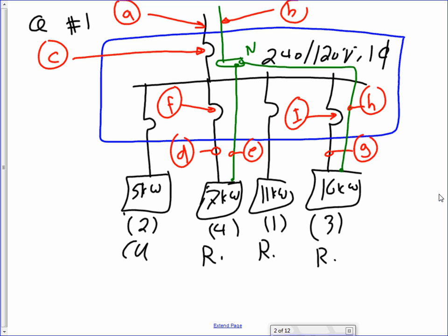So, okay, I'm going to start directly, guys. I'm going to start with sizing A. I do have the calculation here for you. So if you look at A, yesterday we were looking at 220.55, the table 220.55. I want you, Matt, to look at these sizes. Do you guys remember that 5 and 7 are under B? Both of them are under B, right? Remember that column that we were looking at, the table? Both 5 and 7 from table 220.55 are under B. 11 and 16 are under column C. So we're going to find the demand for all these systems.